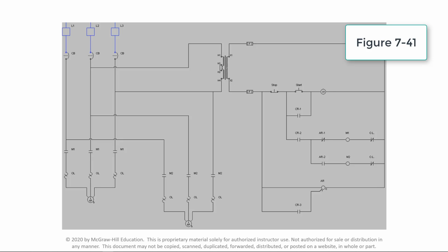Providing a motor control circuit that automatically alternates which pump operates with each start-stop sequence assures that both pumps get equal runtime. When the circuit is first activated, it energizes the first motor, M1. The circuit remains in this state as long as starter coil M1 stays energized.